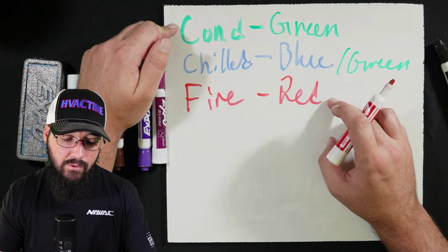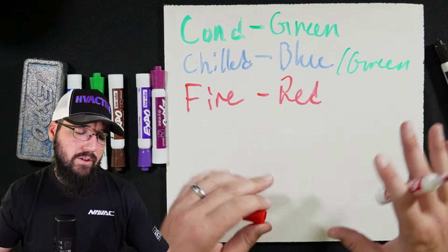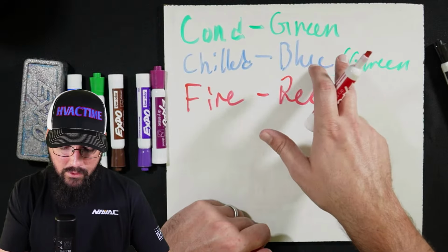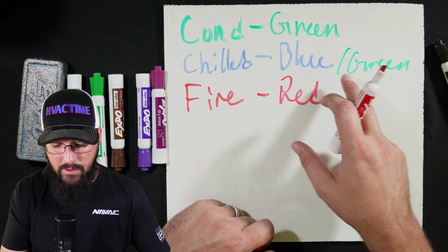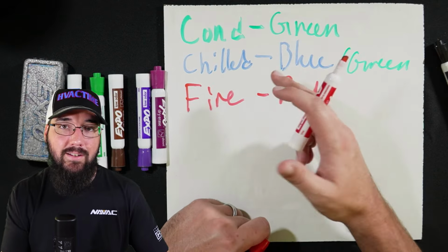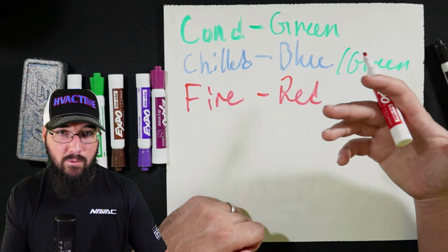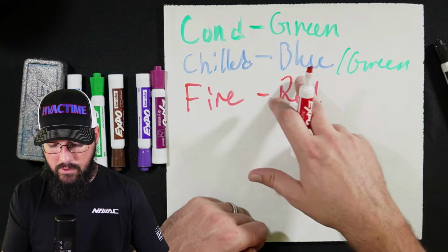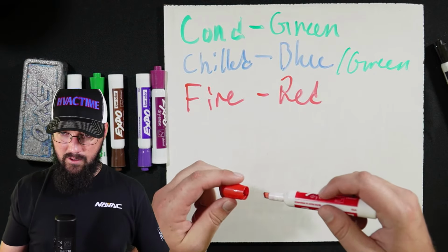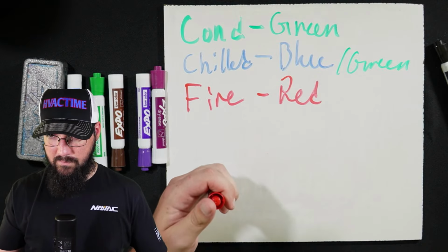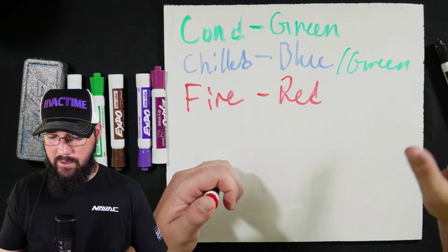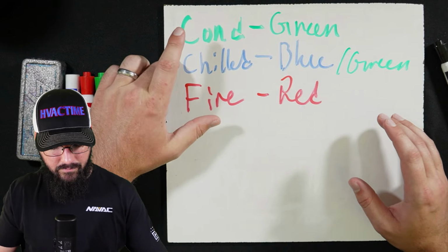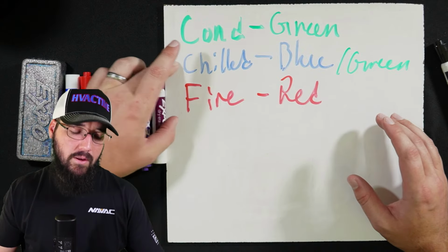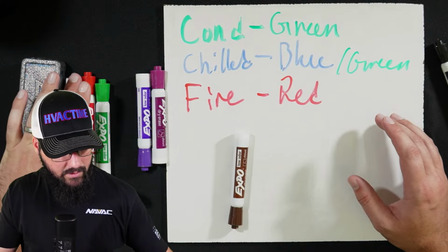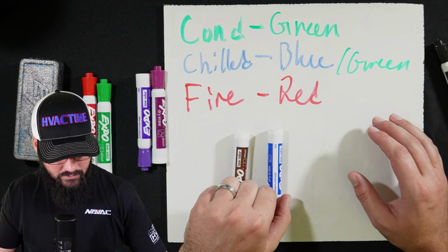And this is one reason why, well, that also gets back to branding. I'm not going to say that. Okay. So condenser water is almost always green. Chilled water is going to be a lot of times blue, but it'll be the insulation itself that's painted, not the physical pipe because the pipe's covered up. Or the chill water could be green. Your fire is going to be red. Glycol loops where it's like pure glycol flowing through them, I don't know what that color would be. Potable water. So we have potable. I think potable may be brown. And I think compressed air is blue. So we can look this up. Let's do this.